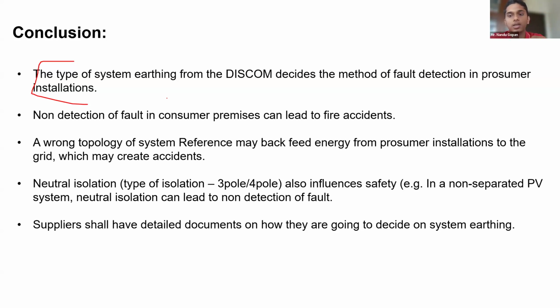You should have a system referencing conductor, and as I explained in the previous slides, you are supposed to change it. So the discom should decide what type of fault detection is done on the prosumer installations, because if they give TT or TNS, TNCS, it will differ. Another important thing is, if there is a fault on the solar side, if you follow IS 732 and size your conductors and overcurrent protective devices properly, you will get selectivity, and only where the earth fault is will it be isolated from the other system.